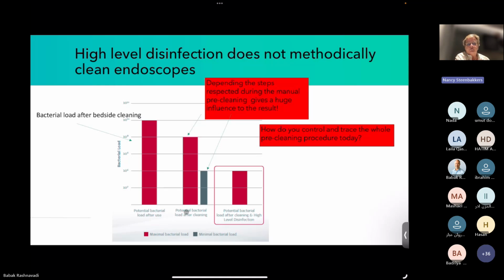Then if you go in the middle, there you have a result of the potential bacterial load after cleaning. That means you go to the sink, you perform your bedside leak test, then you have to rinse and flush all the channels, then you have to brush, and then you have to flush again. This is the whole procedure. But sometimes we see in some endoscopy departments, they don't have the time. There are some emergencies with patients. They cannot respect all these steps. And then you see two different results. The red result is the one where you are missing steps for sure. If you do it in a good way, then you have the gray bar, and that's really a better result.